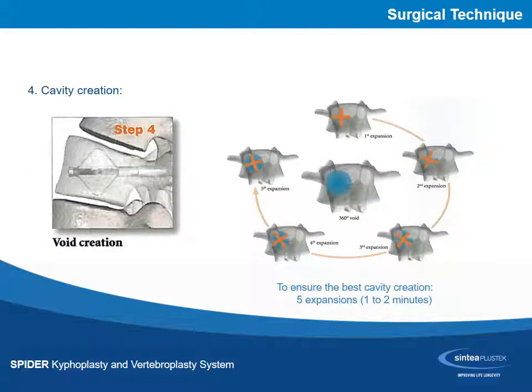Insert the expander until the target is introduced in the first notch. At this point, turn the handle clockwise to expand the tip. The volume of the new cavity should be checked through the expansion graduated scale. Rotate the handle counterclockwise until the device is completely closed. Retract the target from the first notch and insert it into the second notch. The expansion process should be repeated through each of the 5 notches, generating a 360 degrees cavity.